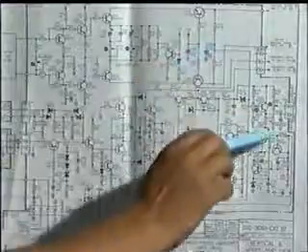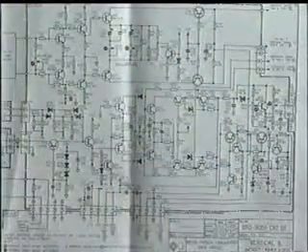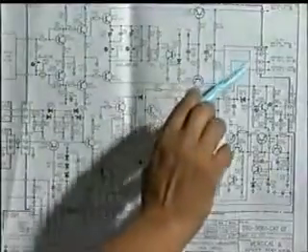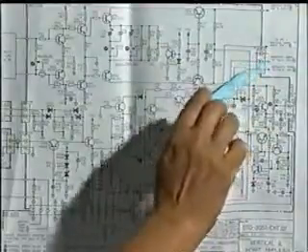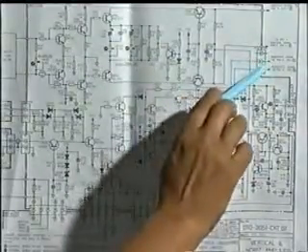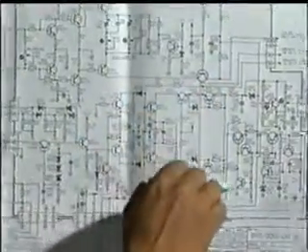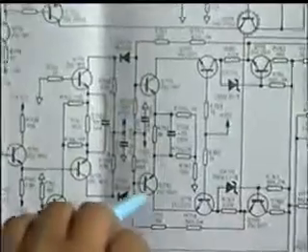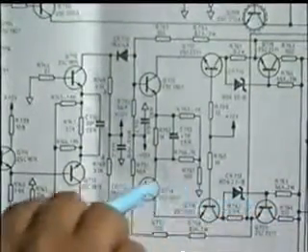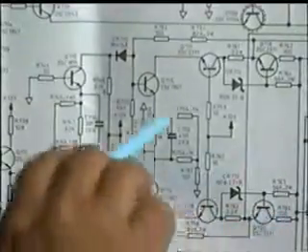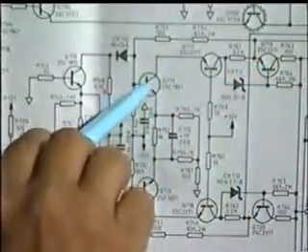This is the circuit diagram of the horizontal stage of the defective CRO, and these points are going to the CRT X1 and X2 plates and coming out from this area. This is the amplifier for one plate, and this is the amplifier for the next plate.